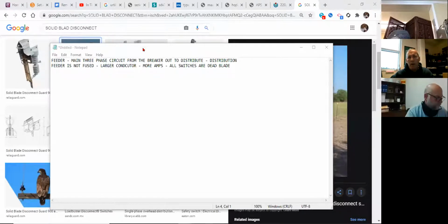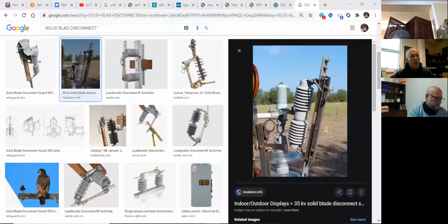And the purpose of feeder line: now that we've got the substation, we've got the ACI to the breaker, and we've got the breaker out to our feeder line, we can install protective devices in our feeder. Then we're going to go into taps and what we do as far as taps are concerned. So while we're sitting on that, we know the definition of feeder. What's the definition of a tap?